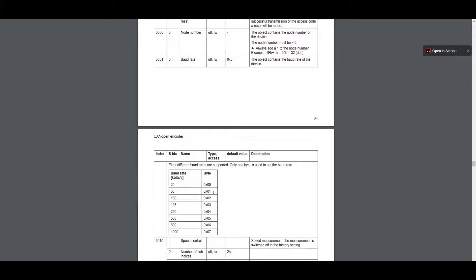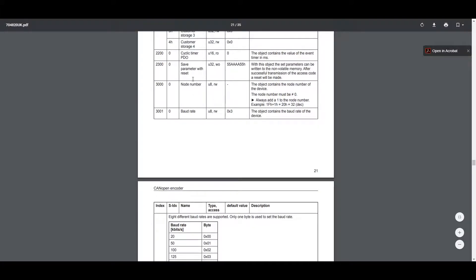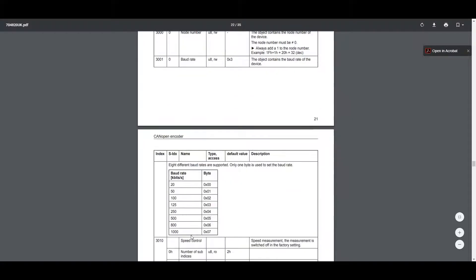So baud rate here, node number, and then the last is the save parameter with reset. And that one has some different values that we enter. Baud rate - the default is a value of 3 which correlates down here in the lookup table to 125. We're going to change the baud rate to 250, so it's going to be a value of 4.